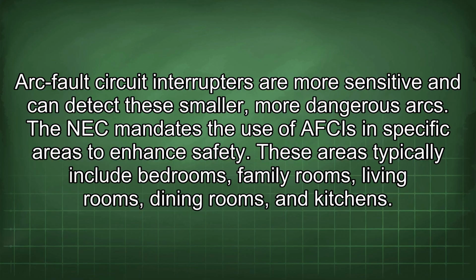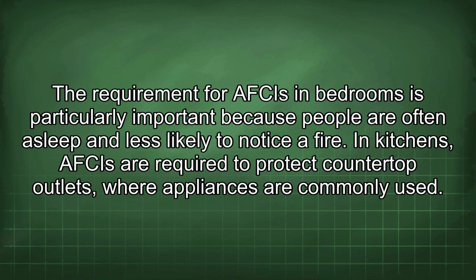The NEC mandates the use of AFCIs in specific areas to enhance safety. These areas typically include bedrooms, family rooms, living rooms, dining rooms, and kitchens. The requirement for AFCIs in bedrooms is particularly important because people are often asleep and less likely to notice a fire. In kitchens, AFCIs are required to protect countertop outlets, where appliances are commonly used.